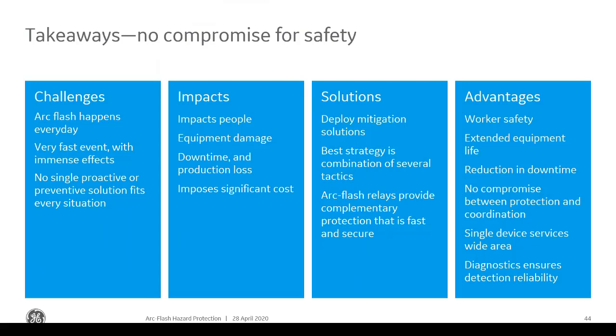So we talked about the challenges of arc flash. It happens, right? A very fast event with immense safety and damage effects. There's no single proactive solution that fits every situation. It's up to what you want to spend, whether it's a green field or brown field, it depends on the application. If you just want a quick fix, it impacts personnel, equipment damage, downtime, production loss, economic loss. Solutions we talked about: deploying those 6 mitigation techniques. We talked extensively about bus protection and the light sensor as being the 2 most effective, combined with a fast acting breaker.